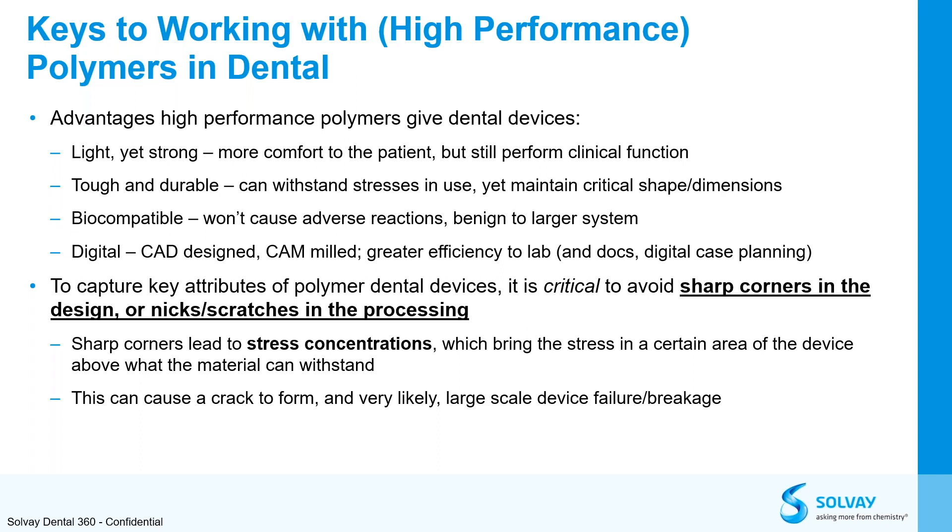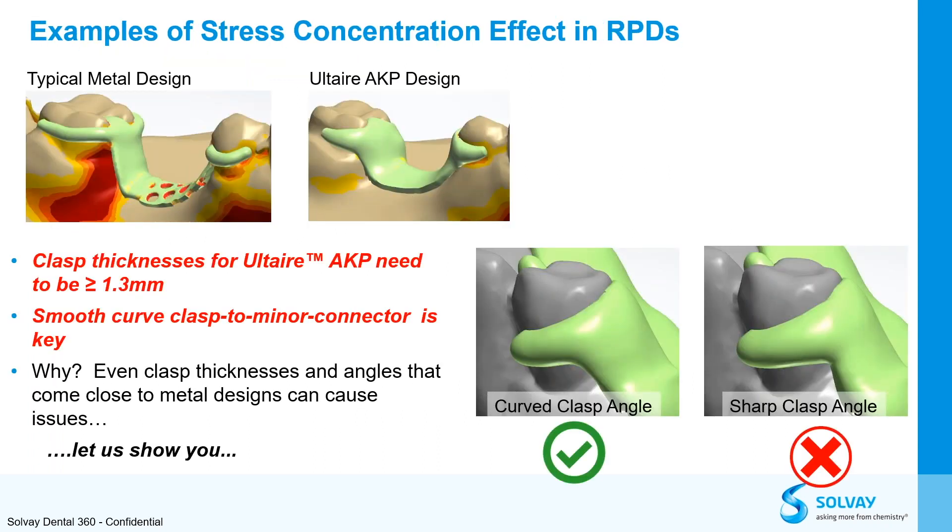However, to ensure a successful process, there are some things we want to avoid, such as sharp corners in the design, or nicks and scratches in the processing, because those can lead to stress concentration points which will cause cracks, breakage, and device failure. As we can see in the picture, the typical metal clasp has a sharp corner — we always want to try to avoid that. With the Ultaire, you want to keep everything round, smooth, and thick enough.